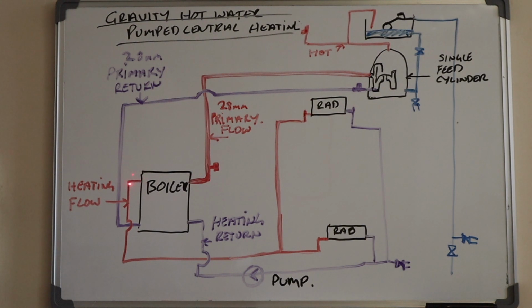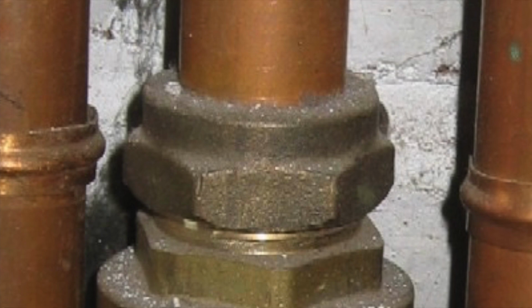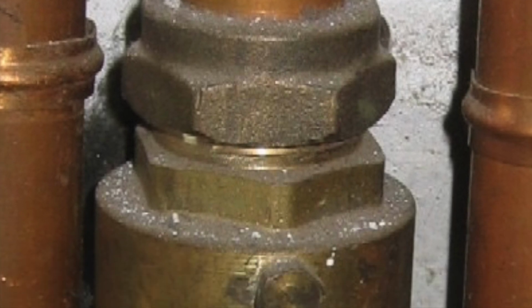Now, if this wasn't designed by going down first and then going up to feed upstairs radiators, we would have needed an anti-gravity valve here to stop the convection flowing around the radiators upstairs when just the hot water's on. But because they went down first before they went up, they didn't put an anti-gravity valve in. It possibly could have still started to circulate around, but it's unlikely with it dropping down first. So when we did go upwards, we always put an anti-gravity valve in. So if you're changing gravity hot water pump central heating and all the pipes go upwards, always check there isn't an anti-gravity valve there. Now, this anti-gravity valve is basically a non-return valve which works to prevent thermosiphoning.